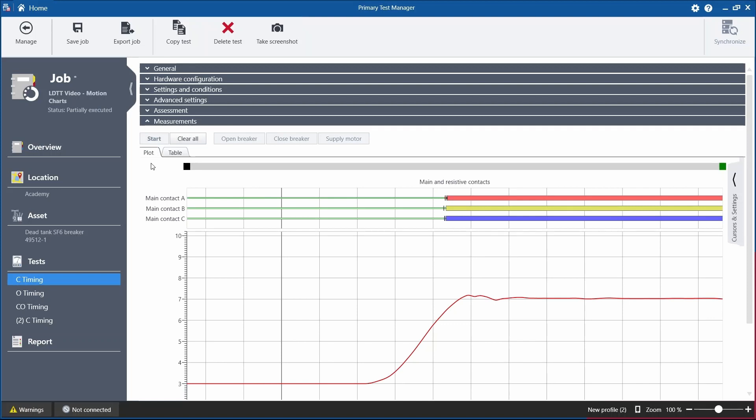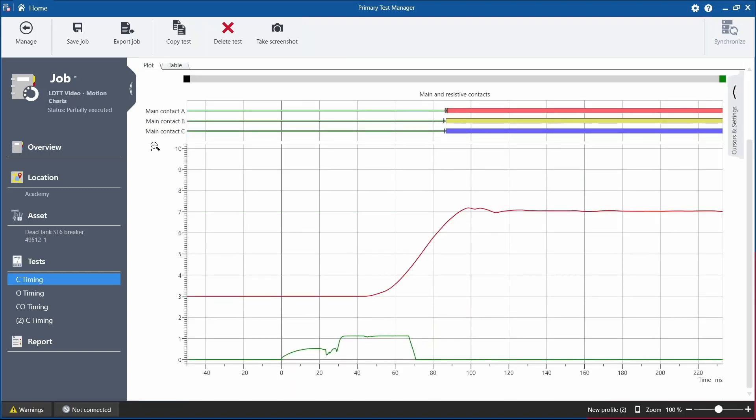With our measurement completed, we can open up in the PTM and go to the plot section here. And here at the top, we can find the status of our main contacts starting in the open position, indicated by the thin green line, and then into the closed position with the red, yellow, and blue solid lines for each respective phase.